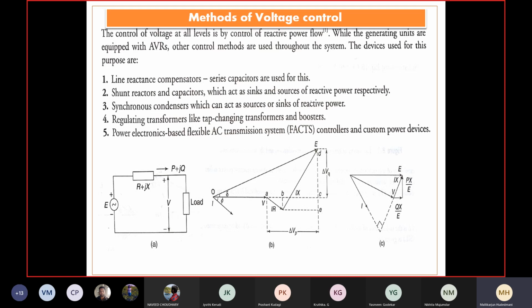Like if we have a transmission line possessing XL as a total reactance, and you want to reduce that, I incorporate a series capacitor XC along with the line, such that XL and XC get compensated and the net reactance offered by the compensated line stands as XL minus XC. So the total reactance XL is now reduced by the compensation adopted through the series capacitor. One concept triggered here is the use of a series capacitor. A capacitor in series with the line reduces the overall reactance of the line, such that more of the reactance part is eliminated and power transfer takes place very effectively. So the additional drop that would have happened due to the reactance is reduced or diminished. This way, reduction of line reactance by a series capacitor is one method.